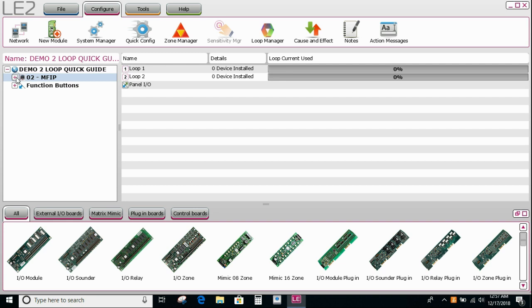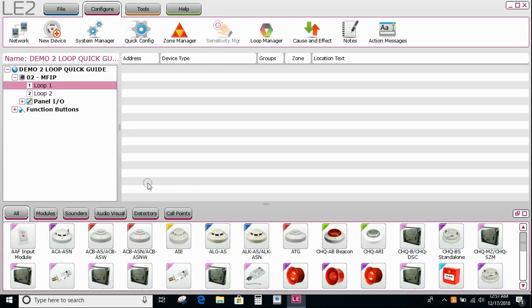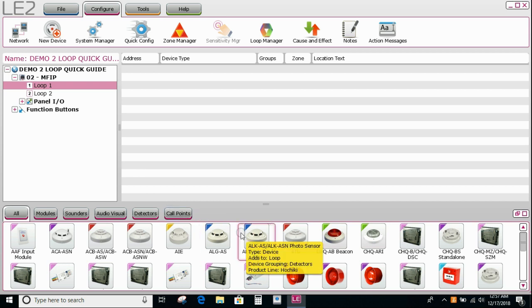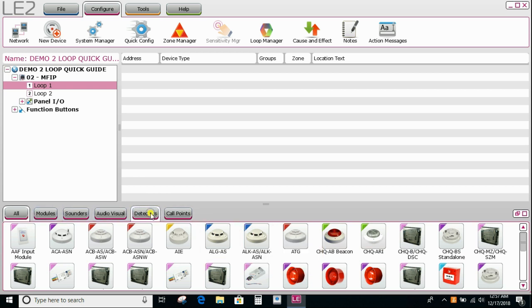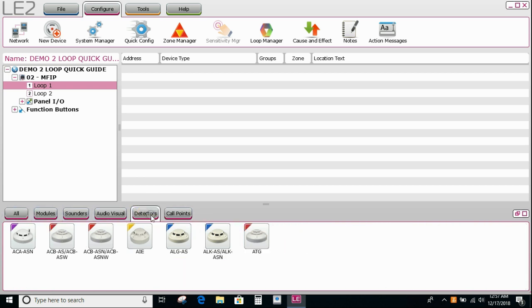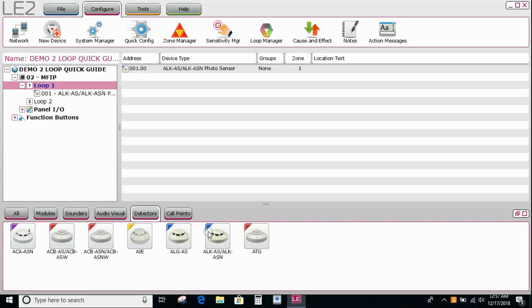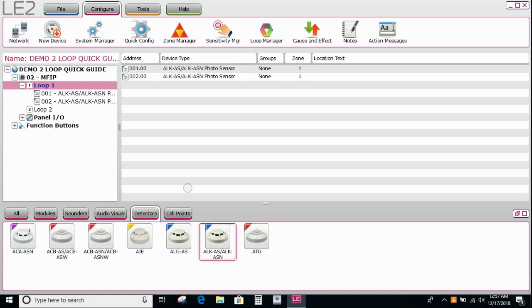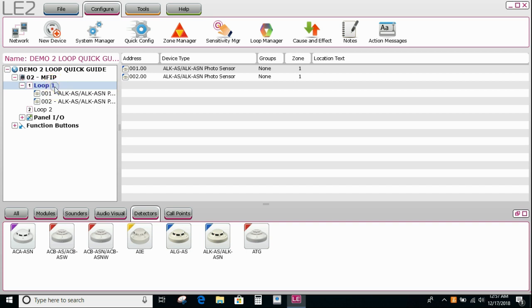So the next thing I need to do is expand this panel and go to the loop. And you can see it opens up the icon bar for the devices. So we can use these filters. So if I want to add detectors, I can just go to detectors. I'm going to double click, and double click will add the detectors at the next available address on the loop that I have selected over in this window. Or if I wanted, I could add it in a different format. If I was adding multiple ones, I might highlight the loop, go to new wizard.